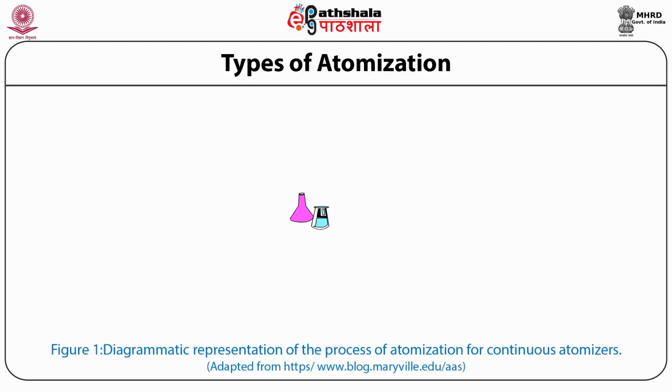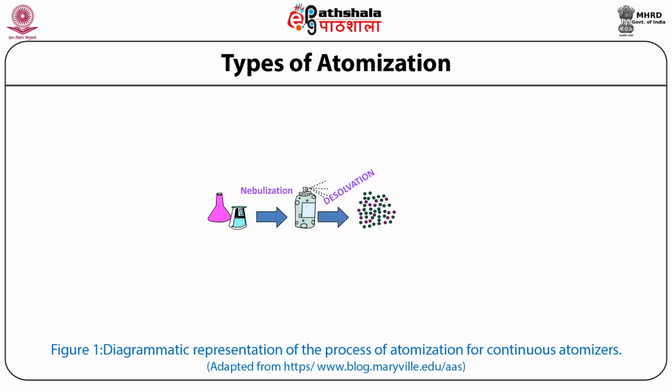This is a diagrammatic representation of the process of atomization for continuous atomizers. The solution or sample under test is nebulized. Desolvation, that is evaporation, is done, followed by dry aerosol formation, wherein volatilization takes place and free atoms are produced.